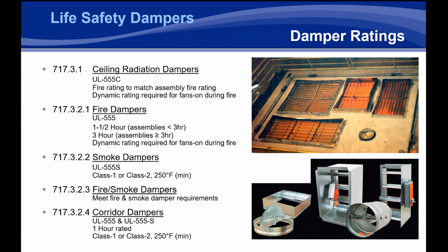Where this came into play is they weren't sure if these fans would continue to run, and some authorities having jurisdiction were requiring that additional smoke detectors be tied into these bathroom ventilation fans to make sure that they shut down in the event of a fire. Now, even before this change, UL had certain fan assemblies tied with dampers that were approved for these static assemblies, these wood truss assemblies being used. With those approvals, UL has reviewed the damper and fan combination and made sure it will not create a dynamic system. UL recently changed their marking guide to fully dictate that.